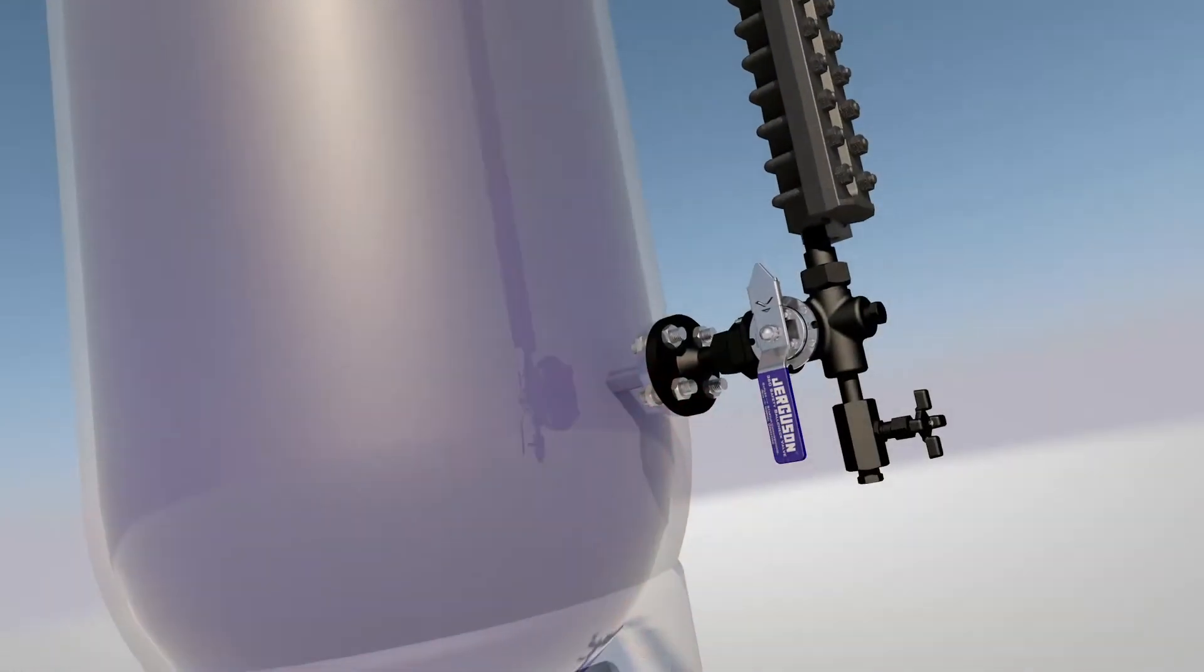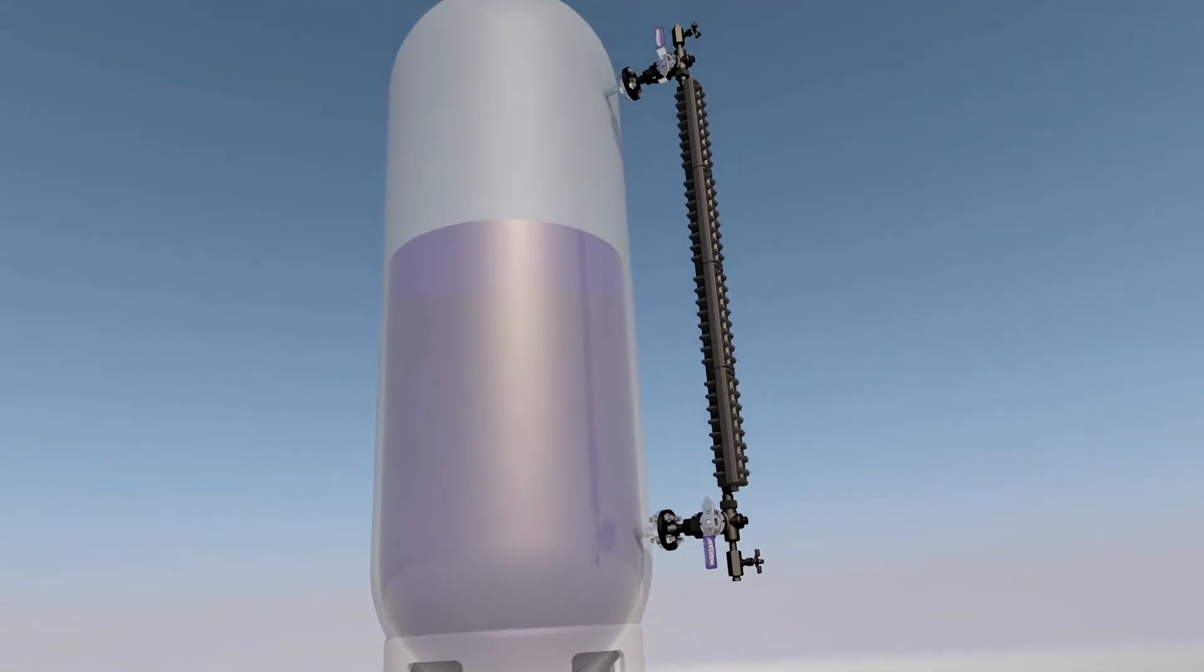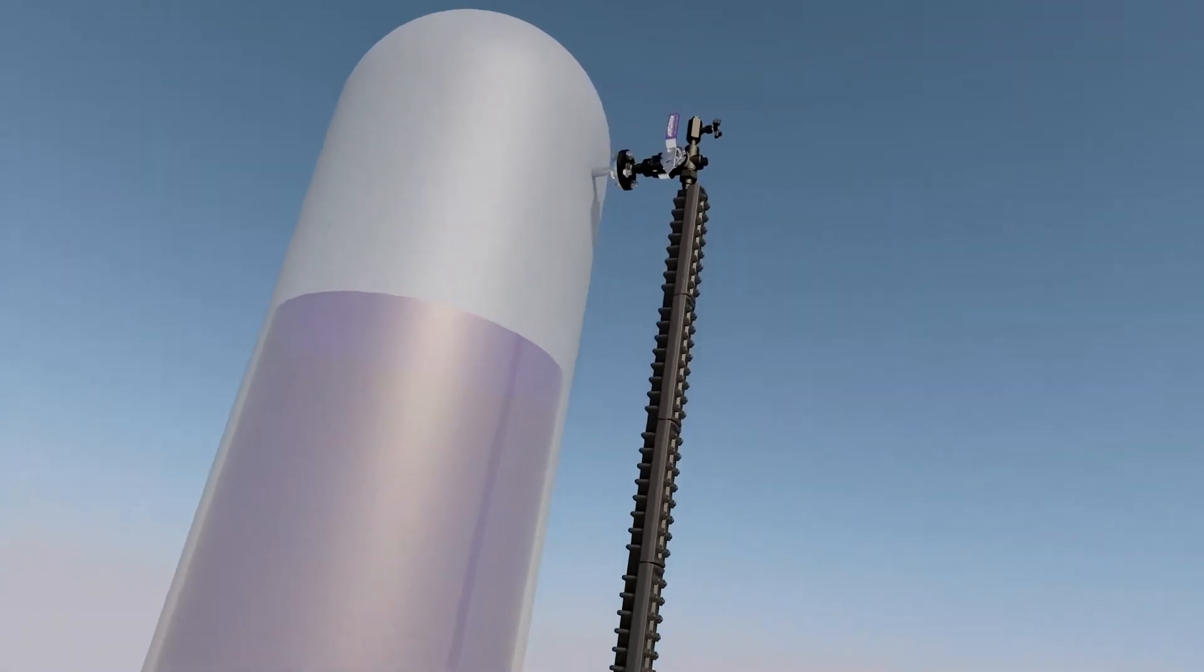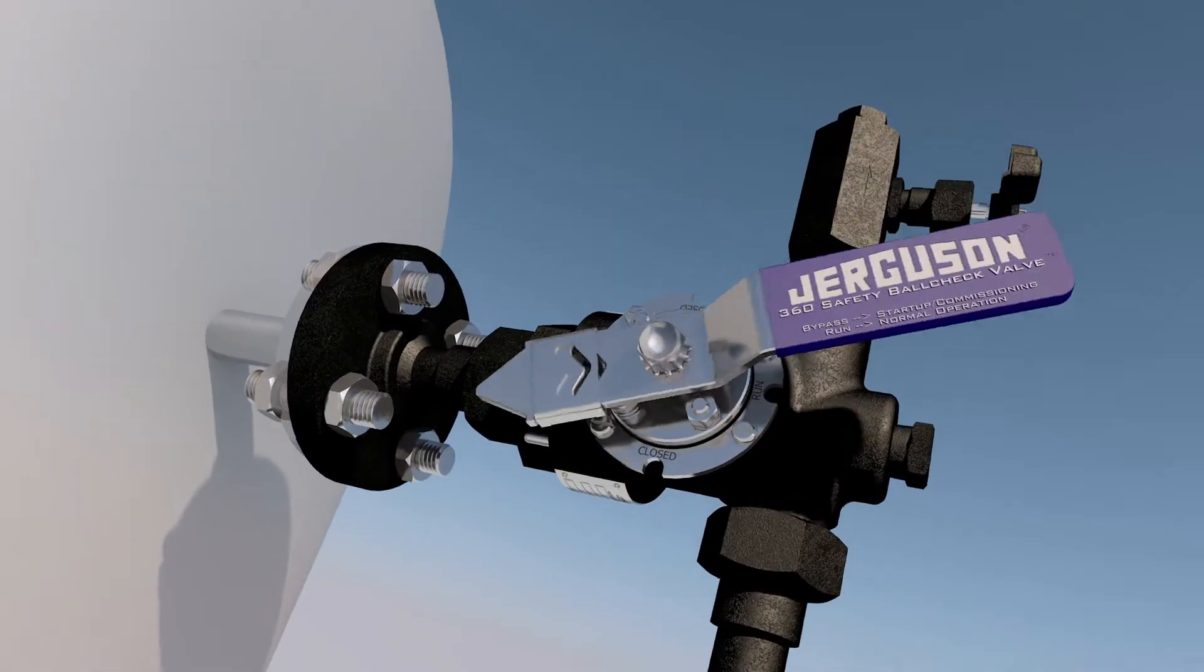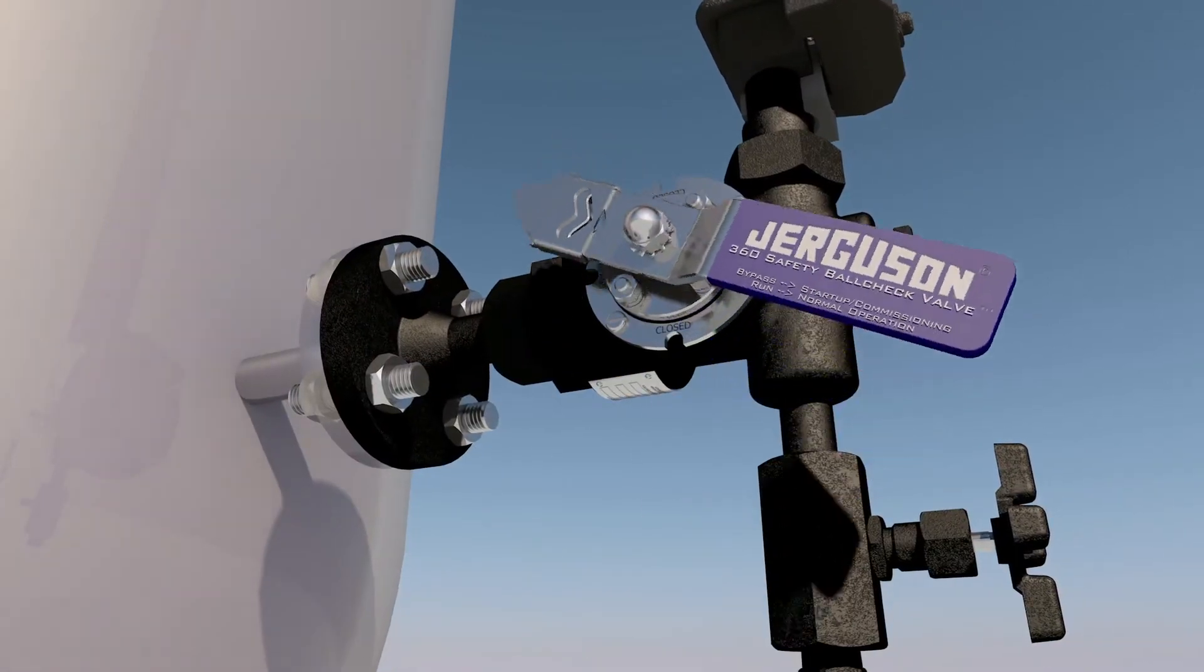The commissioning procedure is quite simple compared to traditional glass gauge ball check valves. When there is already liquid present in the vessel, open the top valve to the bypass position, then the bottom valve.